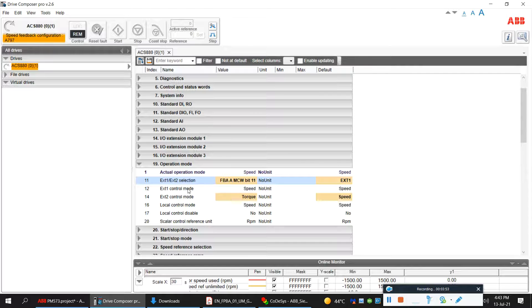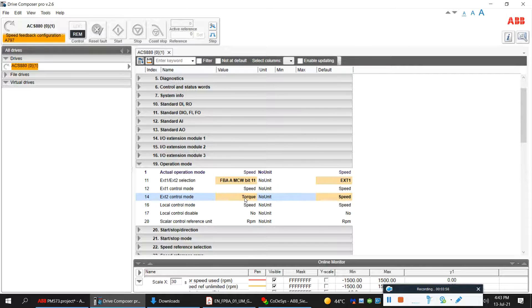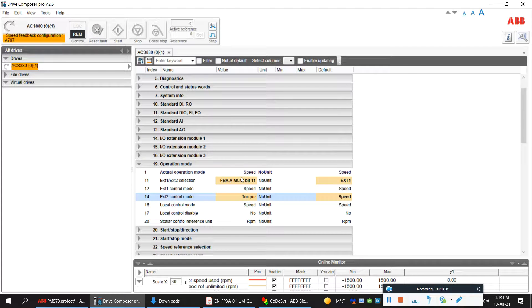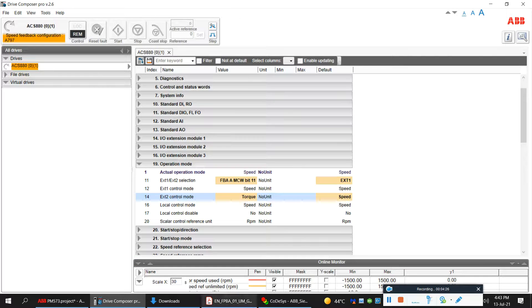I have configured external one as speed and external two as torque. So if bit 11 goes high, that selects torque control. Right now the drive is in speed control mode, and if I activate this bit my drive will go to torque control mode. I'll just show you that.